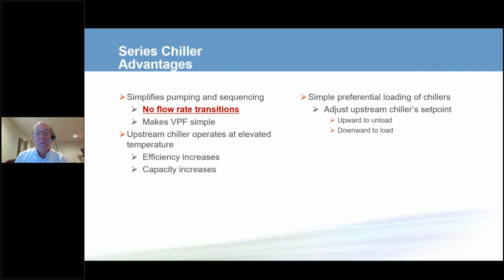This is ideal if you have an application where you're going to have 2 chillers, the system's unlikely to expand, you're going to a higher than 8 degrees C delta T, and you want to do variable primary flow. Really consider putting the chillers in series. It provides great benefits for the building owner. It simplifies things, and it takes you and the building owner away from the hardest part of variable primary flow systems, since there is 0 flow rate transition when we bring that second chiller online.